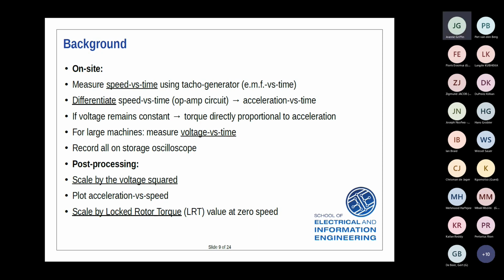Okay, so how do we do the test on site? Well, we measure a speed versus time trace using a tacho generator, as I said, normally handheld, quite small. And we produce two signals from it. The one signal is this, effectively voltage versus time, which is directly proportional to the speed. And then we use an op-amp circuit to differentiate it, which will then produce a real-time acceleration versus time trace. And we put both of those channels into a recording oscilloscope, which we can then download later. So we're using a tacho generator to produce a speed signal. We're differentiating it immediately with the op-amp circuit to produce an acceleration signal.